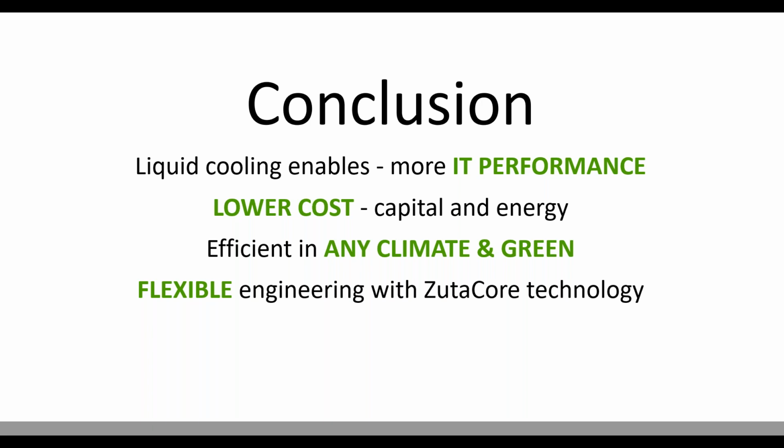The result is they're able to capture the stranded power, increase the capacity of the data center, and lower their PUE, all in one solution. This is what I believe is key: it can be done seamlessly. It can be done in a live data center without disrupting the current HVAC system. And we think that's very, very important.